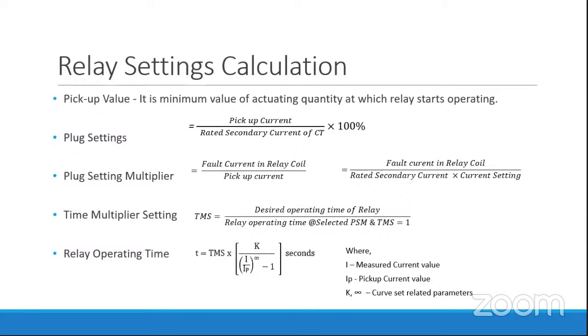Plug setting, which is based on the pickup value and the rated CT current. Based on this we need to give certain settings to the relay, which will be getting inputs from the CTs. The plug setting value is the pickup current divided by the rated secondary current of the CT, in terms of percentage. Plug setting multiplier is the ratio of the fault current in the relay coil to the pickup current. The time multiplier setting, TMS, means the ratio of the desired operating time of the relay to the relay operating time selected for the selected PSM and TMS at 1.